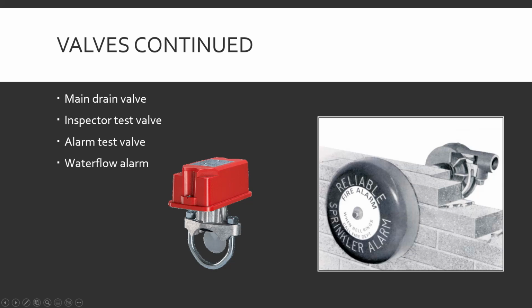Sweet. Break a sprinkler head, or the alarm goes off, or there's an actual fire, or what have you. Water starts flowing through the system and out of the sprinkler head somewhere. The turbulence of the water causes this little flapper valve to move. The little controller here goes, I'm moving, I'm flowing water, I have to sound a water flow alarm. And that sets off the alarm.